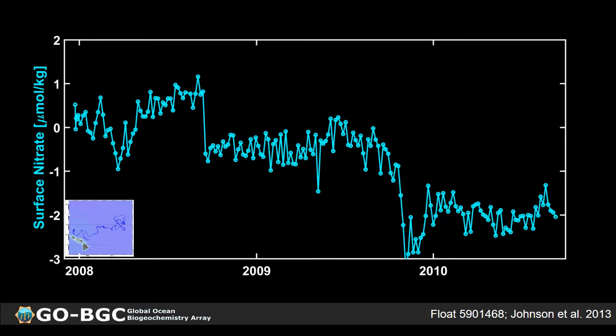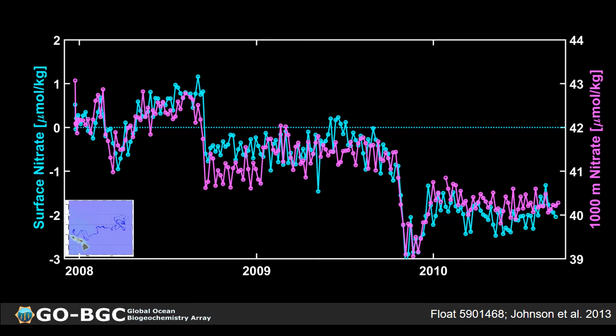If you plot the 1,000-meter nitrate data on top of this, you can see that the patterns of the surface nitrate and the 1,000-meter data are very coherent. Based on the HOT data, we also know that the 1,000-meter nitrate is very stable in this region. So what this implies is that the sensor drift is manifesting in an offset manner. In other words, if the surface nitrate is reading low by 2 micromoles per kilogram, then the 1,000-meter nitrate is also reading low by about 2 micromoles per kilogram. Using this observation, we can correct both the surface and the 1,000-meter nitrate by forcing the surface nitrate to be 0 throughout the life of the float.